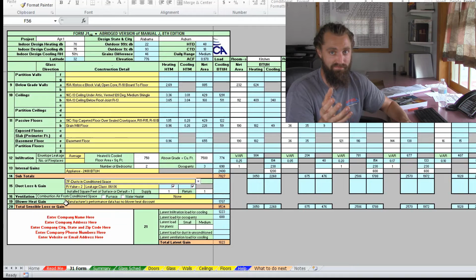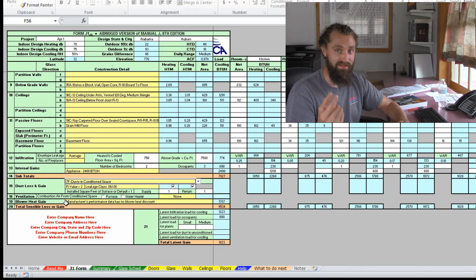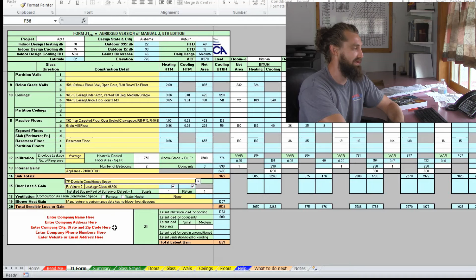If you had anywhere that you were pulling combustion air for a furnace, like if you had a 90% furnace and you're drawing combustion air from a mechanical room internal to the house, we need to account for that here. If you have a water heater doing the same thing with atmospheric venting, this is a big one, because it's drawing air from your house to create that stack effect in the chimney. So we'd want to account for that here.